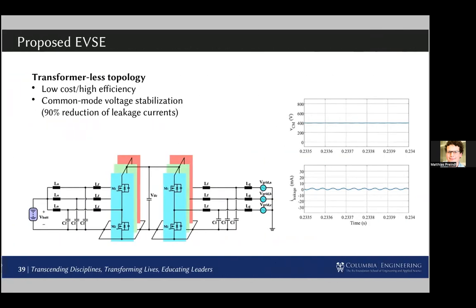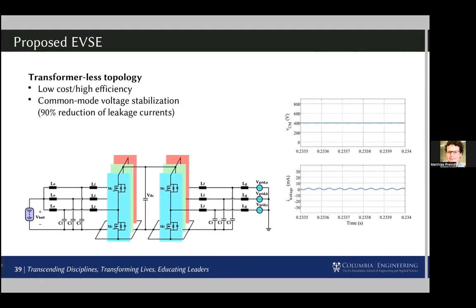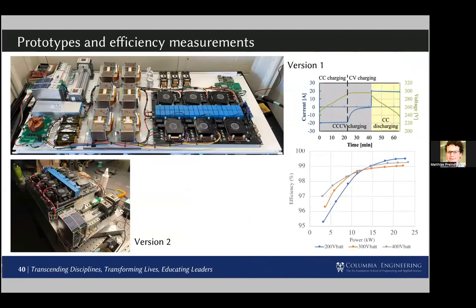The way we are thinking about it is to combine 6 or multiples of 6 phase legs together and form what we call a transformerless charger. They are fully balanced and stabilize the common mode, so the leakage remains significantly below the threshold, and this path reduces the leakage current by 90%. There are some examples. The upper one was the first prototype that was very slow switching. Then we completed version 2 about a year and a half ago, and we are now working on version 3, which is about 1/5 of the size of version 2.